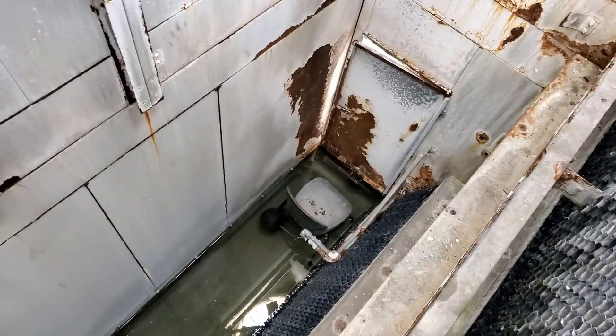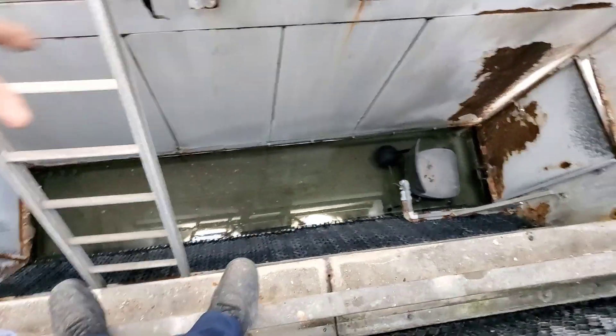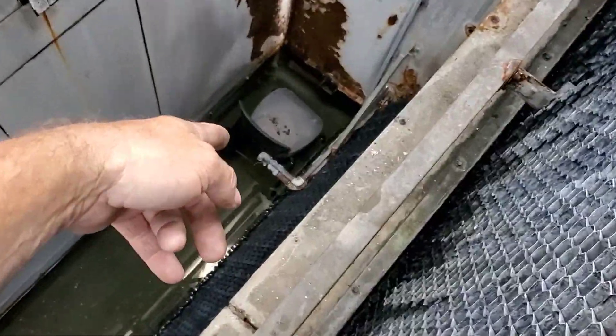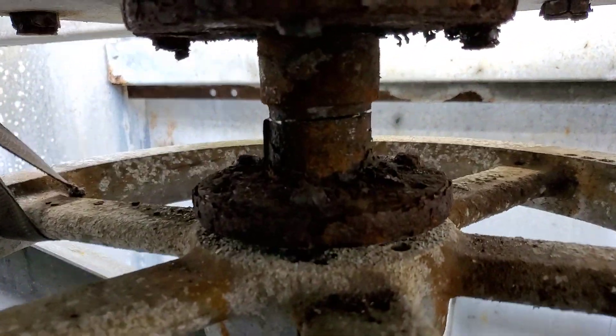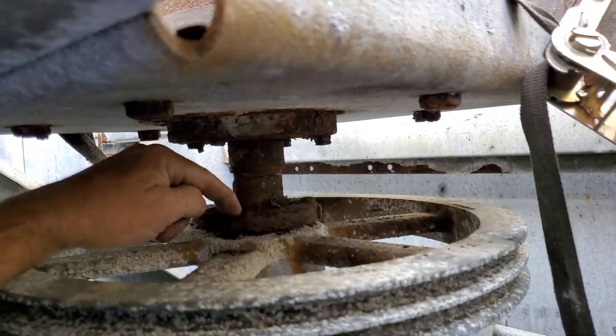What is up? Up inside one of these Marley piece of shit towers. I hate these things. The design is shite. There's water where you walk in through the door, there's no railing down there, you have to do things like stick chairs down there. Look at the fucking corrosion on this — this is like a six-year-old tower and it's worse than like 10, 15 year old ones.